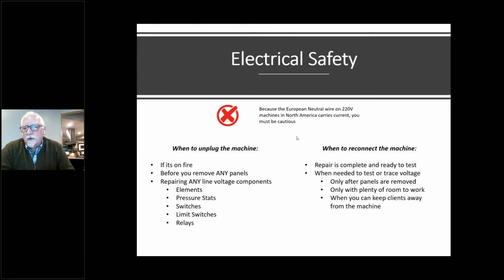But there are circumstances when you have to have the machine connected. Obviously, when the machine is complete and you've done your repair and you have to test it. But some things, when you're testing trace voltage, you're trying to make sure that you're actually getting voltage to motors, getting voltage to heating elements, things like that. You do have to have the machine plugged in while you test it, but you also have to be careful. Make sure that the panels are far away. Make sure that whatever employee is milling around trying to service a customer is kept away from the machine.